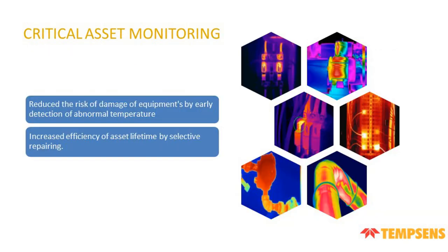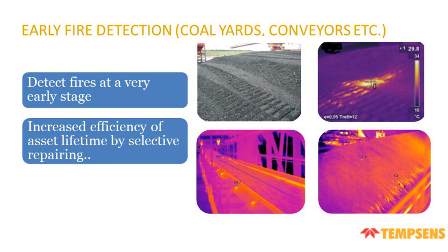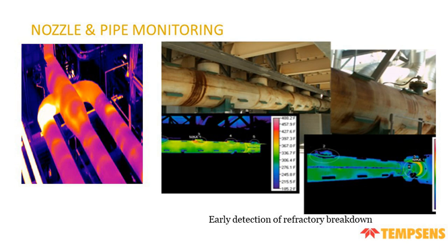Critical asset monitoring. Reduce the risk of damage to equipment by earlier detection of abnormal temperature, and increase efficiency of asset lifetime by selective repairing. These are more advantages of the thermal imaging system. Earlier fire detection, coal yard and conveyor, etc. Detect fire at a very early stage. Nozzle and pipe monitoring: earlier detection of refractory breakdown as well as failure and leakage of pipeline we find from the thermal imaging system.